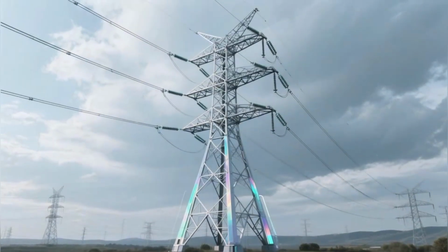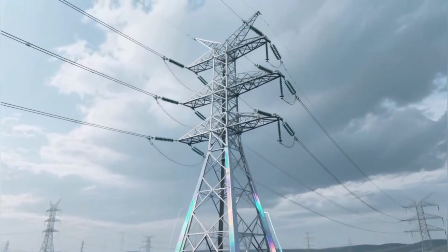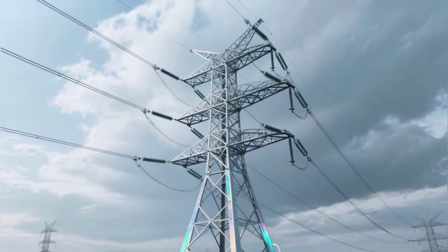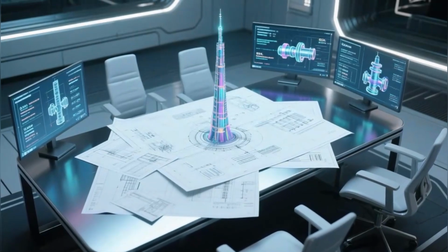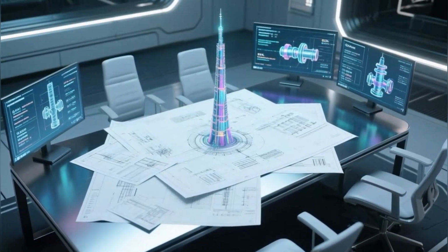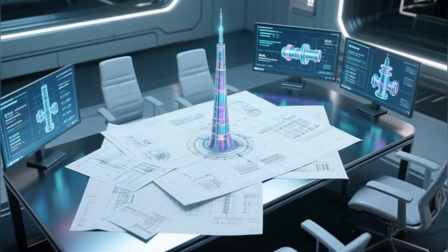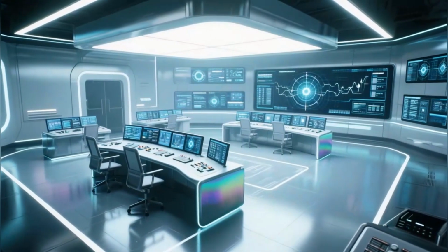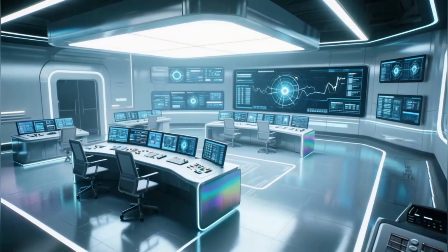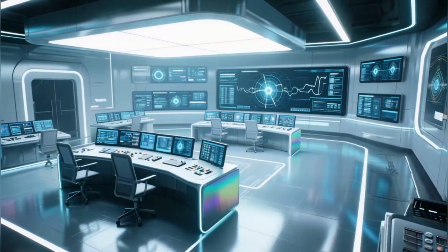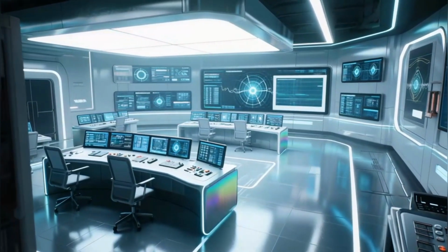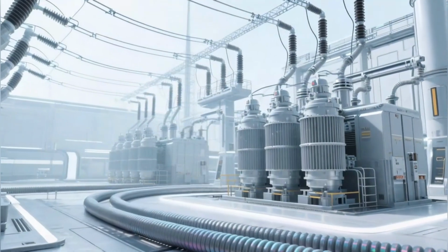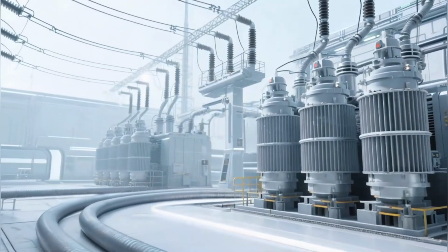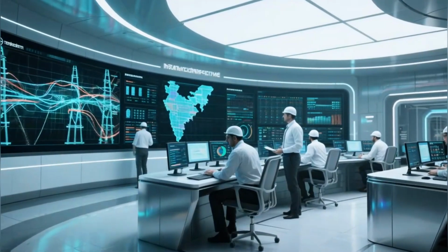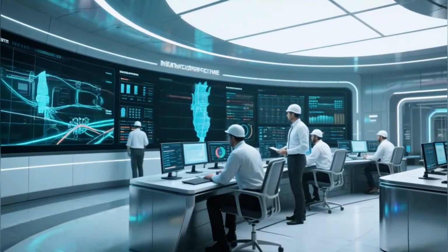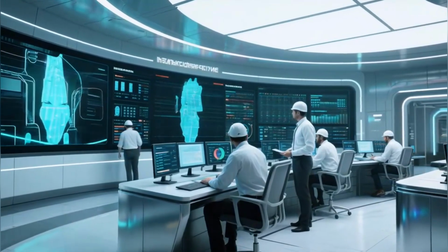Several challenges had to be solved. 1. Insulation coordination at plus 800 kV: corona effects, clearance distances, tower design optimization. 2. Thermal management: handling 8 GW continuously, valve cooling systems. 3. Multi-terminal control: master control coordination, power dispatch, balancing. 4. DC fault handling. Unlike AC, DC has no natural zero crossing. Fault currents rise extremely fast. Protection design had to be extremely robust. 5. System stability: interaction with India's AC network, avoiding oscillations, managing dynamic disturbances.